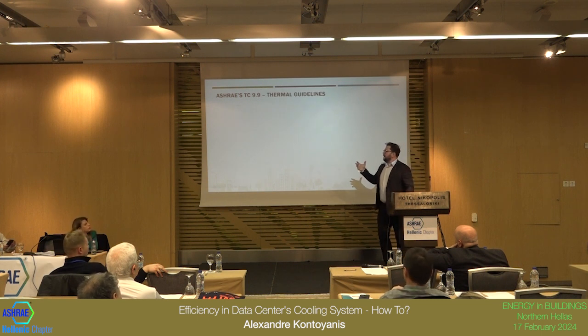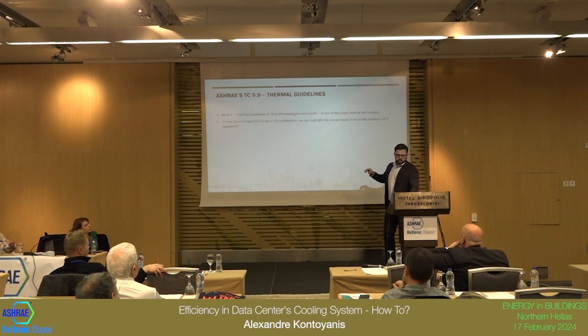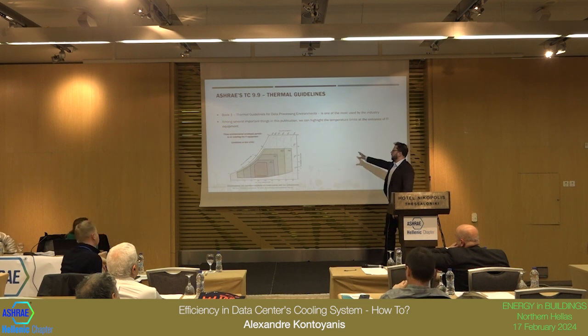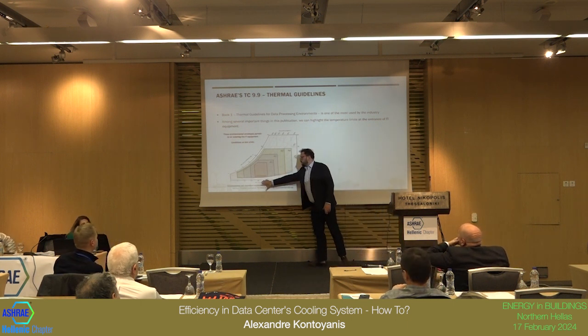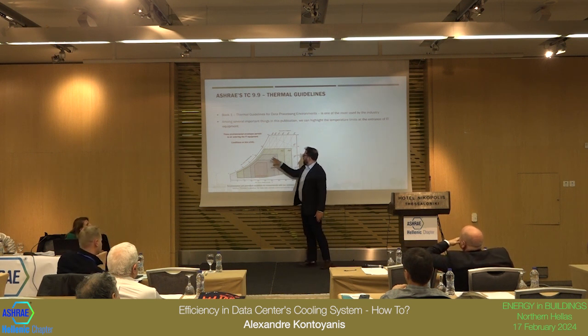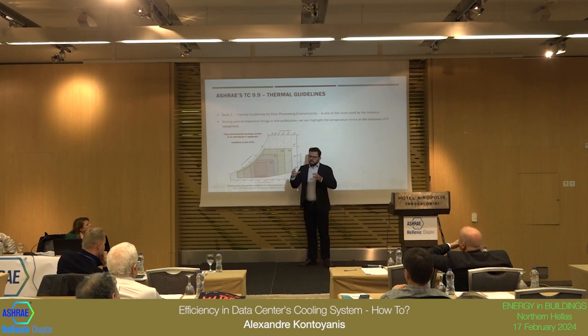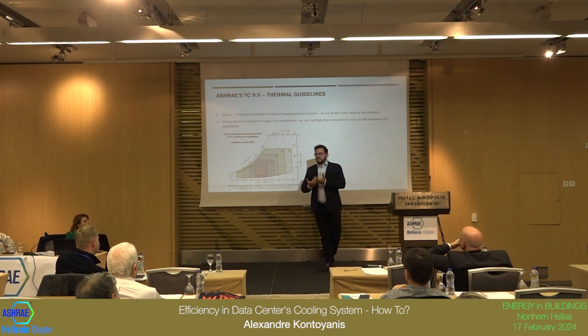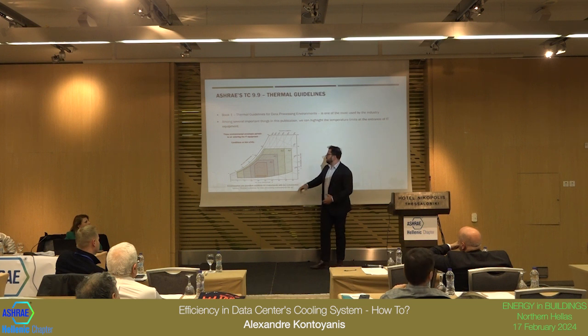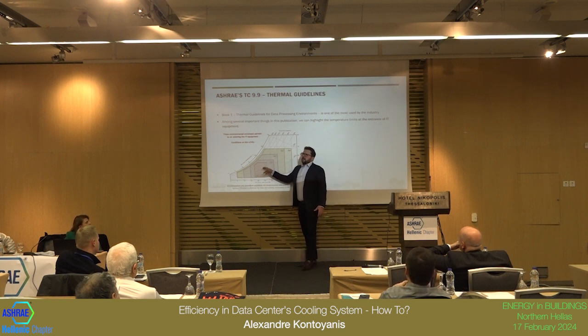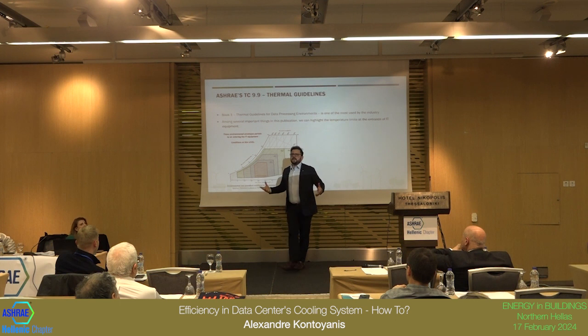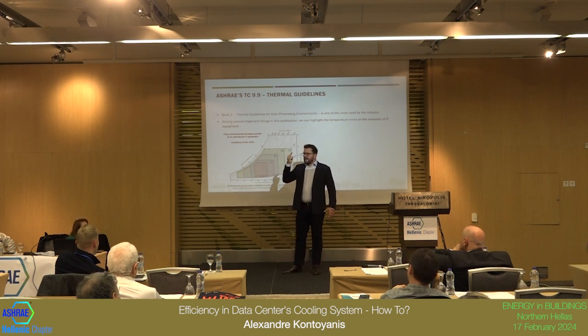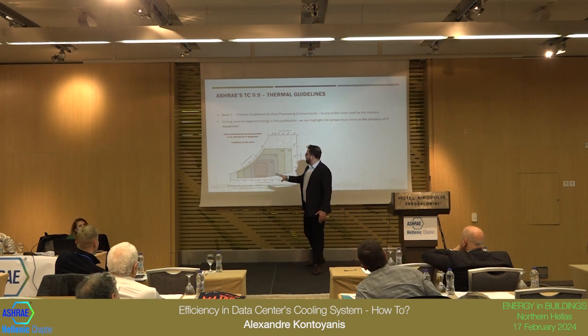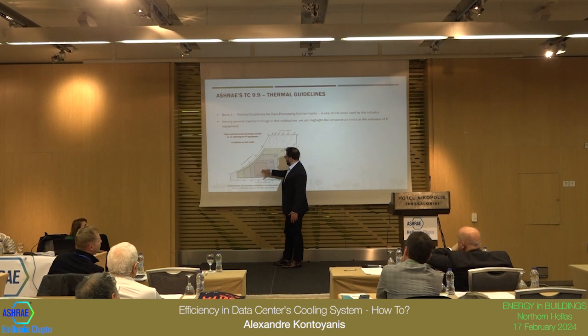They talk about a lot of things, but the main thing is the temperatures we are looking for in a data center. As you can see here, in the psychrometric chart, we have 5 areas. A red one we call the recommended envelope. It means the temperature of the air at the entrance of the IT, that is important, at the entrance of the IT should be here. In 2001, this area was a point. Can you imagine controlling a huge data center to achieve one temperature at one humidity? It's almost impossible. Now you have this area, and you can choose whatever you want.